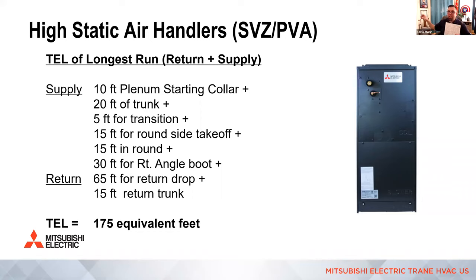This is that branch duct that's for that longest run. And now in this example, there's just 15 feet of round branch duct going over to a right angle boot that's in the floor. So that's the longest run. You'll notice it's very, very simple. There's not a lot of turns, there's not stack heads, there's not all kinds of crazy stuff in here. But I did this on purpose to show you the high values.